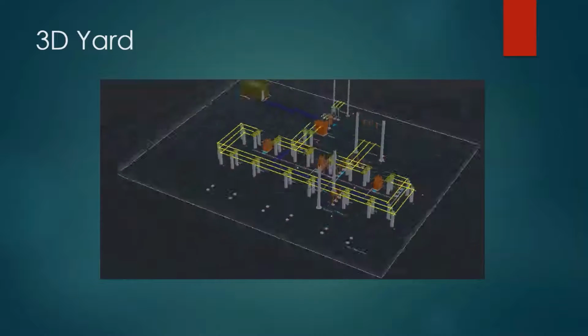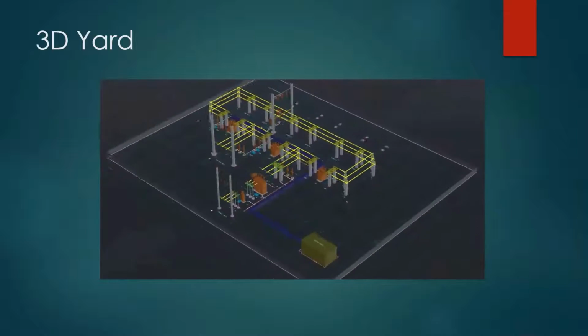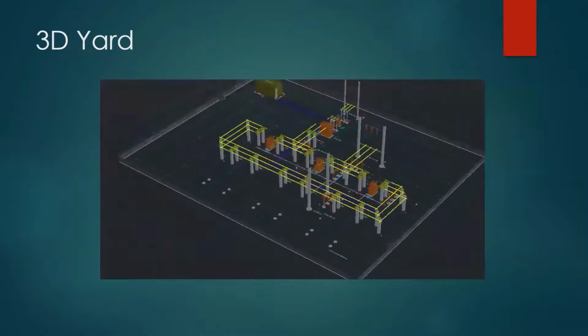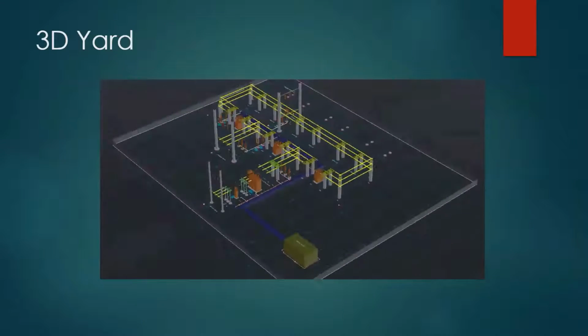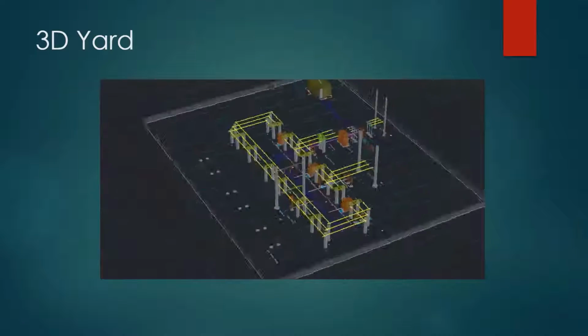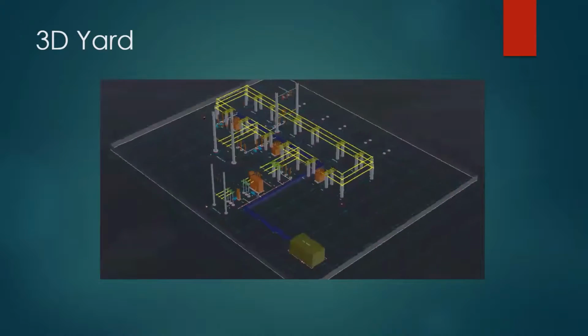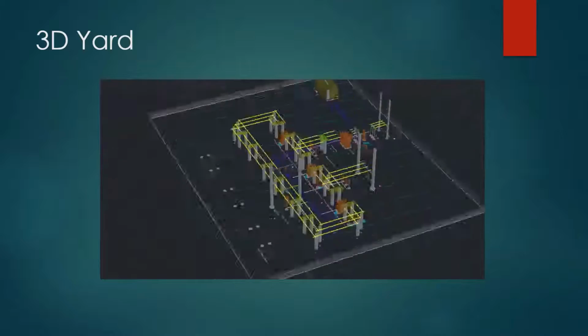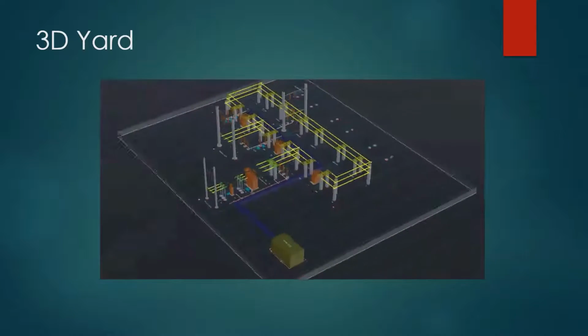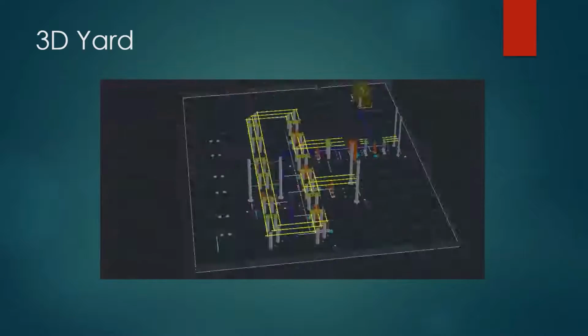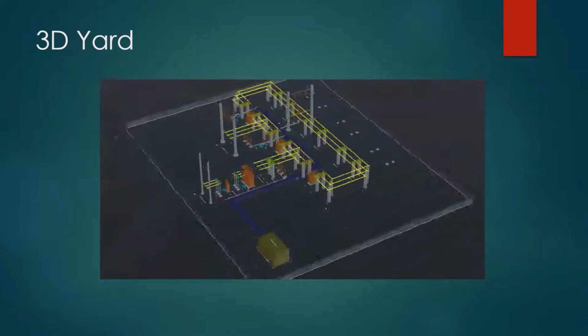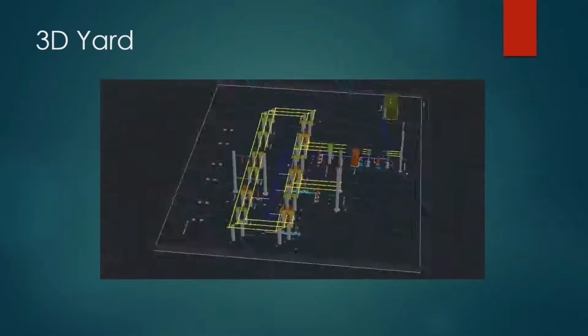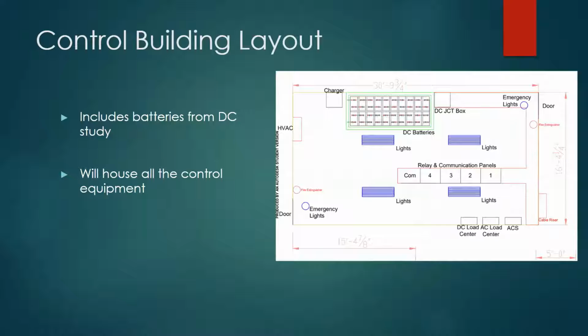So this is a 3D render of our substation yard. You can see the dark blue cable trench, the light blue grounding grid, and then all of our major equipment and the likes. The bus work is 7 feet apart. This was chosen because 7 feet will stop any voltage from arcing from line to line, thus ensuring safety in the substation. Finally, for physical layout, we have our control building layout.